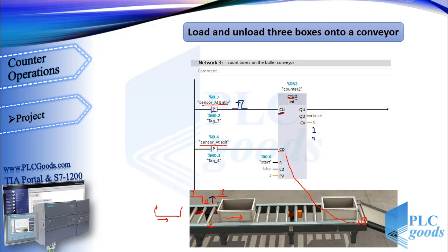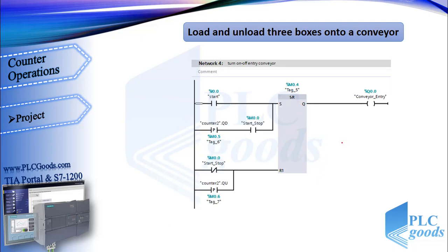With the next boxes, the current value will be 2 and then 3, which equals the preset value. At this time, the first output QU of the counter will be on. In the same way, the second sensor makes the counter value decrease to 0, at which time the QD output will be on. I've also used the start push button to reset this counter at start time.